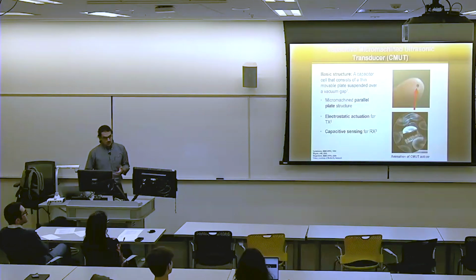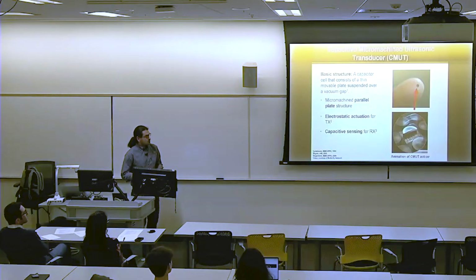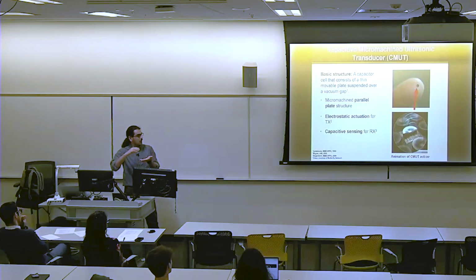This brings us to capacitive micromachined ultrasonic transducers. These are novel ultrasonic transducers fabricated in a clean room facility, the same way cell phone chips are fabricated. At the micron level, they have two electrodes: the bottom electrode is fixed, while the top electrode moves under electrostatic actuation, allowing them to generate and receive ultrasonic waves.